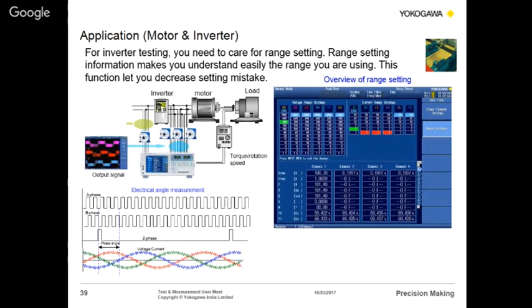Okay, and this is the speed and torque sensor output, which is again fed to the power analyzer so that it can calculate the mechanical power and the input electrical power. Here, there is an option of calculating 4 kinds of efficiencies. One is the inverter efficiency. The inverter efficiency can be calculated by 3-phase output divided by single phase input.